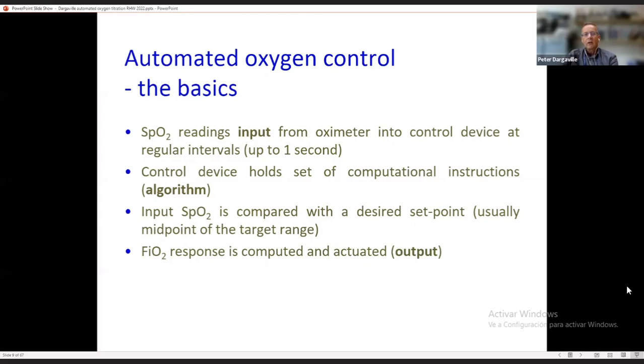That control device holds a set of computational instructions, which is what we call an algorithm. The algorithm takes the inputs, past and present, compares the SpO2 input with the desired set point, usually the midpoint of the target range, and then determines an FiO2 response, a change or no change from the current value, that's computed and then automatically actuated, and that's the output.